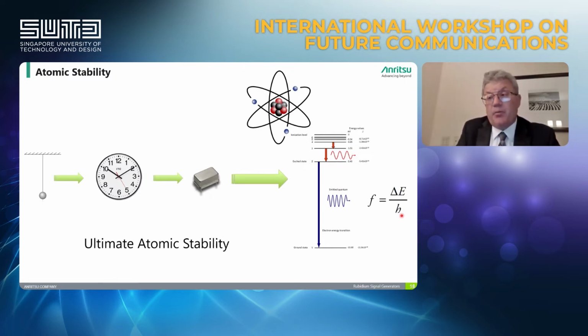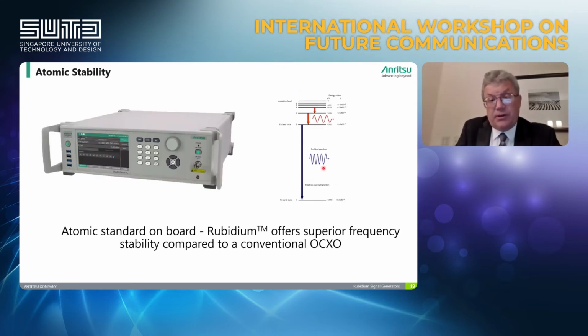That's why we achieve radically better frequency accuracy and stability. So as an option, we implement an atomic standard inside this signal generator, which offers superior frequency stability compared to conventional oven crystal oscillators.